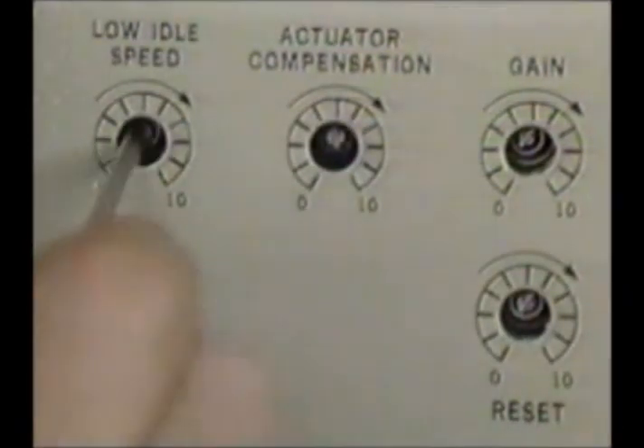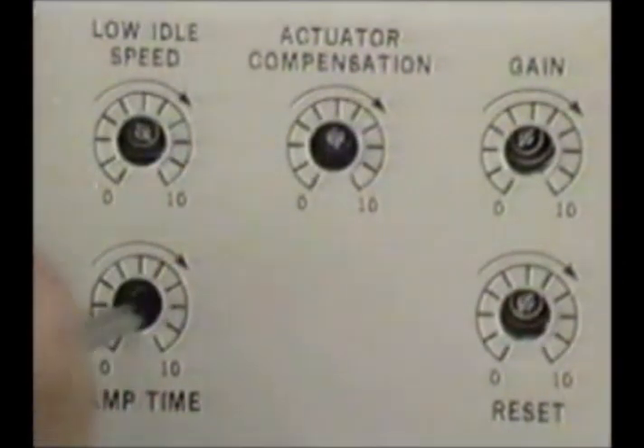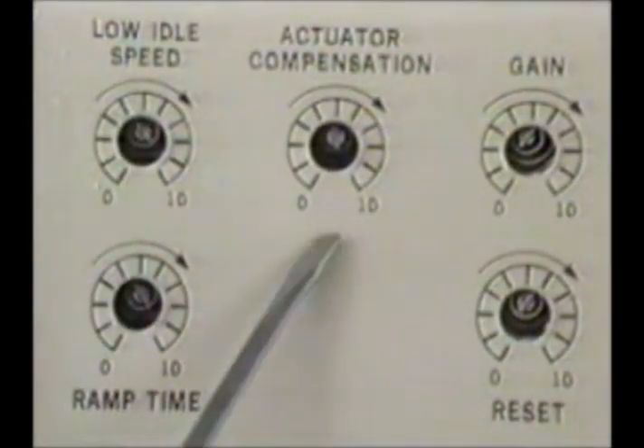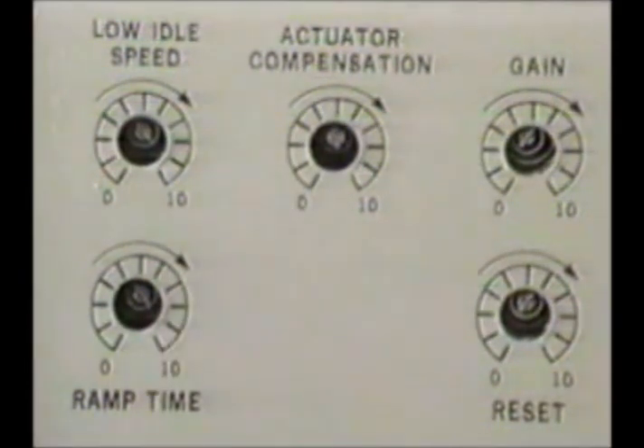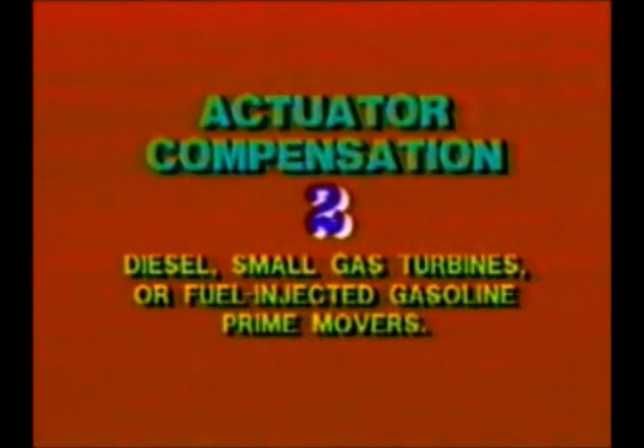The low idle speed potentiometer, we're going to preset full clockwise. The ramp time potentiometer, we're going to set to maximum amount of time, which is full clockwise. The actuator compensation potentiometer is a new potentiometer we didn't have on our old 2301 control. This will allow you to run on a variety of prime movers. We want you to set this actuator compensation at 2 on your 0 to 10 dial if you have a diesel engine, small gas turbine, or fuel-injected gasoline prime mover. We want you to set it up to 6 on the 0 to 10 scale for a carbureted gas or gasoline prime mover, medium to large gas turbines, and steam turbine prime movers.